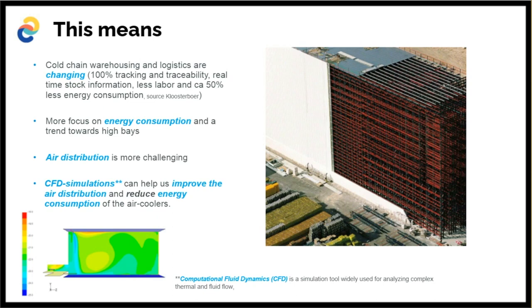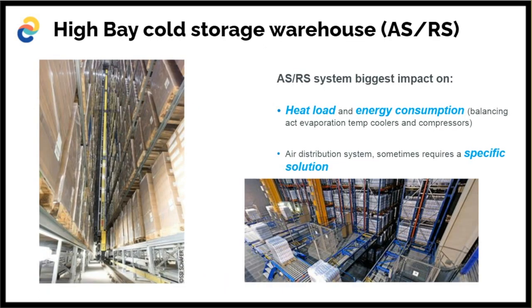By the way, CFD is computational fluid dynamics. It's a simulation tool where we can predict what the temperature and air distribution throughout the high bay is going to be. Very handy. Now you see here on the left this big crane, and that is what an ASRS system generally looks like. It's a big crane, maybe four or five in one room, going up and down and back and forth all the time. And therefore, it has an impact on our air distribution, but also on our heat loads. So the heat load calculation should take these big cranes into account. And in terms of energy consumption, we have to have a very narrow balancing act between the evaporation temperature of the coolers and the compressors. And sometimes this air distribution system requires a specific solution.